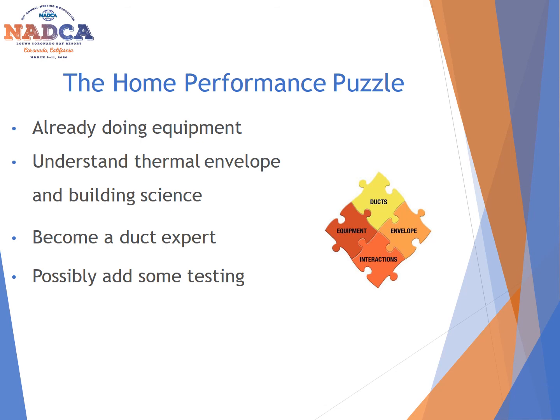As we're going through this presentation, you have to realize that it was developed by NADCA for the entire group of HVAC duct cleaners that are out there. A lot of them are already providing and servicing equipment. So when we're talking about the home performance puzzle, we're talking about all of these pieces, even though we may not service equipment, but that is a big piece of the puzzle. Understanding the thermal envelope of the building and the building science in general plays into a lot of what we do when it comes to duct cleaning, as well as any other services that we provide, especially when it comes to cleanliness of a facility. In order to be proficient, we need to understand how airflow works. We need to understand how duct systems work and how they correlate together in order to create a healthy, clean environment. A good way to figure this out is by doing some testing, which we're going to talk about in the next slide.